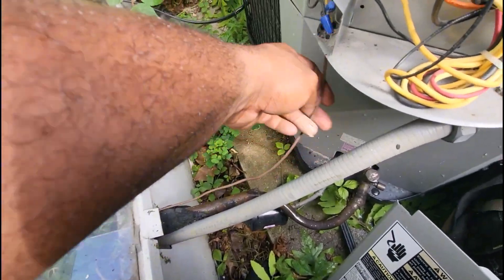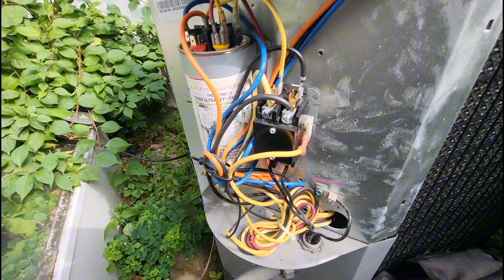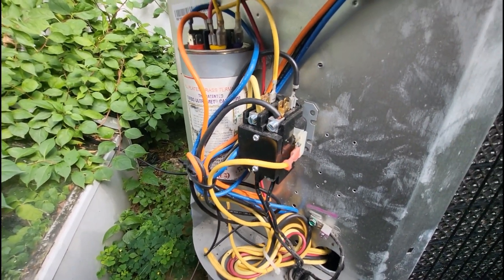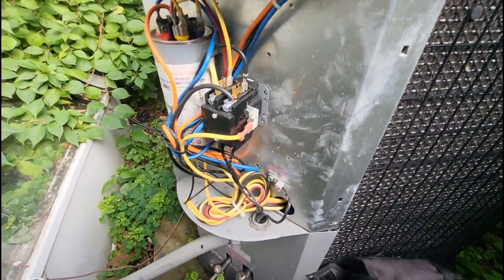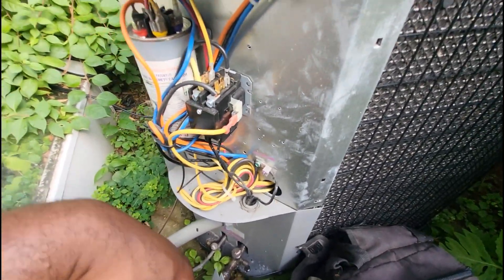This is a straight AC system — they have a gas boiler with baseboards and radiators for heat, but the air handler inside doesn't have electric heat. The issue was the contactor coil out here was shorted, so the customer needed a new contactor. But no one knew where the breaker was to turn this unit off, and nothing inside was labeled.